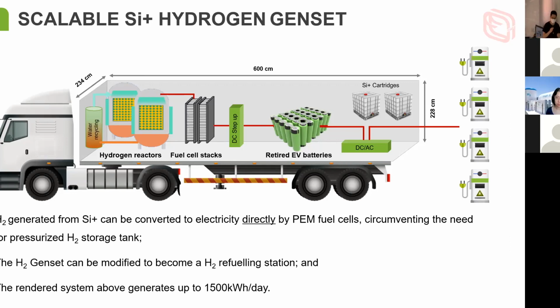Another problem came up with a hospital, I recall, during Hurricane Katrina. The hospital powered up its backup generators, but it actually didn't work. Not because the generator failed, but because of the plug, the connector between the generator and the building's power supply. So with all these backup gensets around the world, does it really work? Yes, the machine does. But does it really connect? Actually, no one knows.